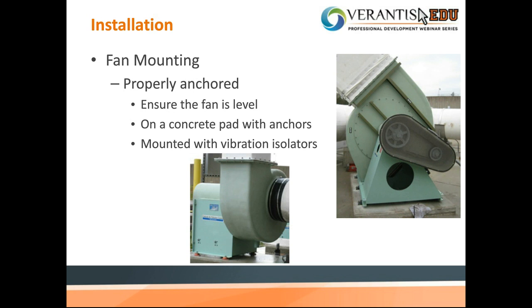If you have a concrete pad with anchors, sometimes vibration isolators are mandatory for the particular location that you're installing. There's a whole bunch of different vibration isolators available. There's rubber mounts, there's spring mounts, there's even just an isolated pad that you can set your fan on. Those particular pictures, both fans on the slide show rubber mounts.